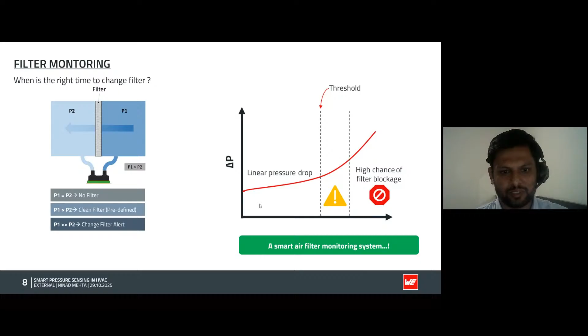Other examples are fan failure or leakage detection, as we saw for airflow monitoring. If there is a leakage somewhere in the vents, then in normal operation the airflow or pressure values from the sensors are more or less very linear. But whenever there is a leakage, the pressure starts to drop slowly, or you see changes in the performance of the compressor or the motor, where the compressor needs to work more than it should in normal operation. That's where you see these abnormal behaviors, and this could also be alerted: okay, there is a leakage in the system, where I need to take active action, find the root cause, and stop it from malfunctioning.